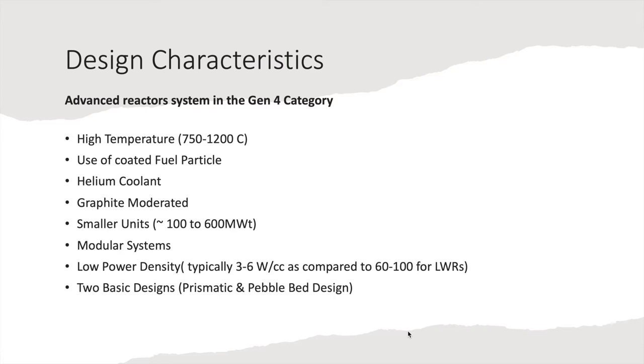According to the International Atomic Energy Agency, any reactor with an output of less than 300 megawatt electrical is known as a small reactor. If the reactors are made on an assembly line and can be transported to the site using rails, roads, etc., they are also known as modular — hence small and modular. The typical power density is 3 to 6 watts per cubic centimeter, as compared to 60 to 100 for a conventional light water reactor.